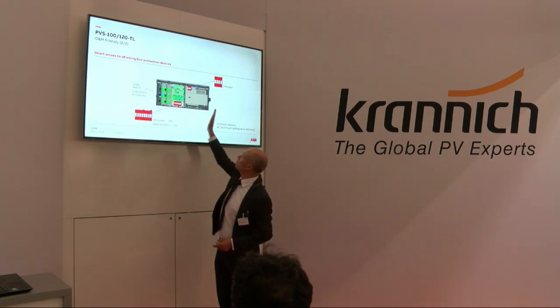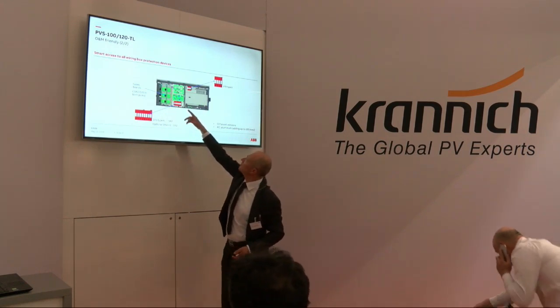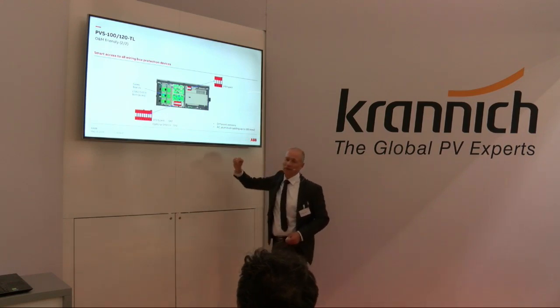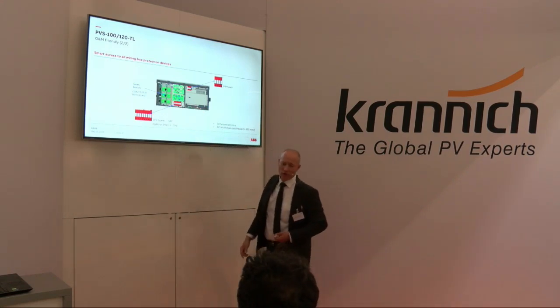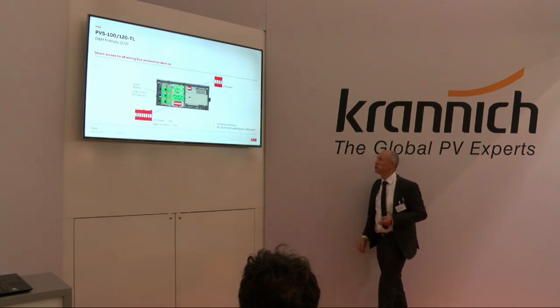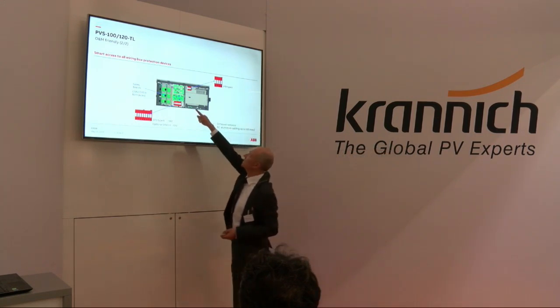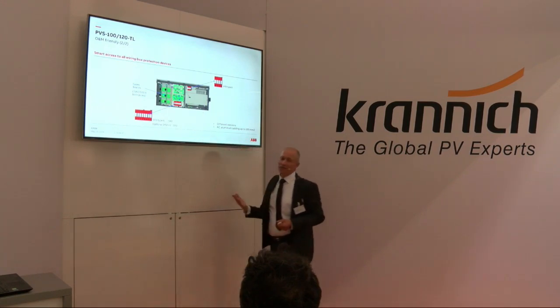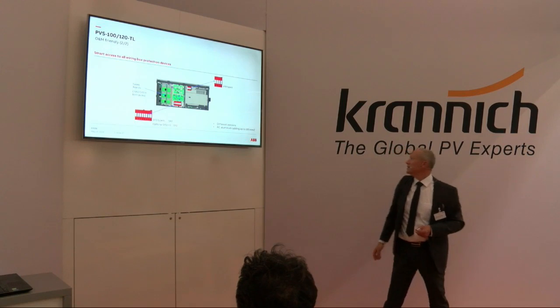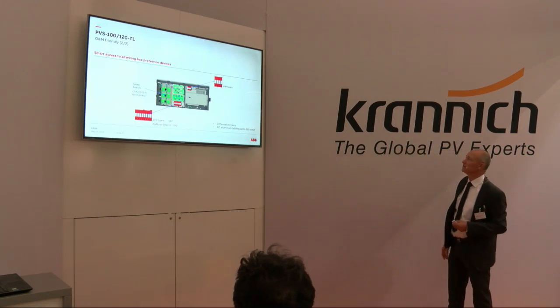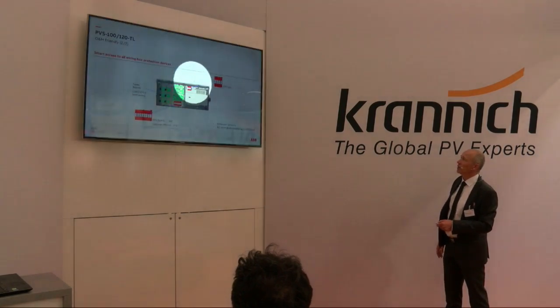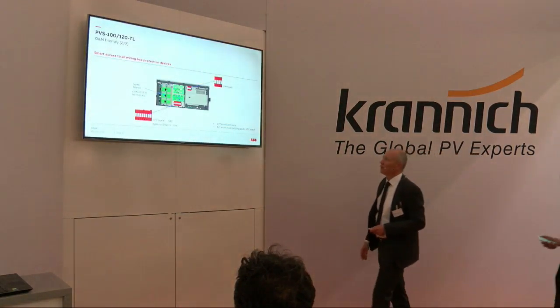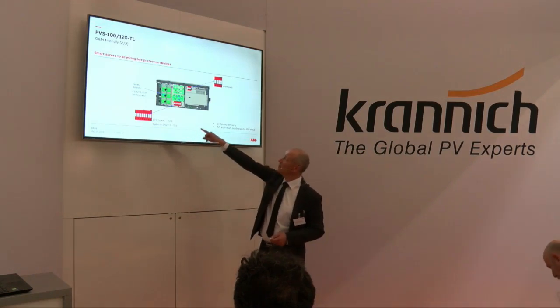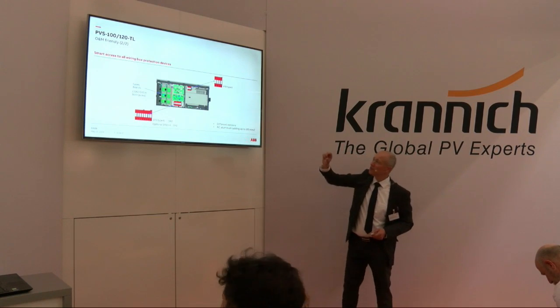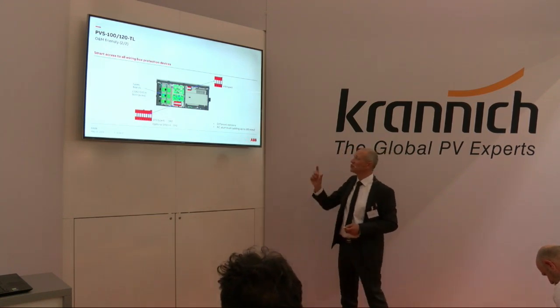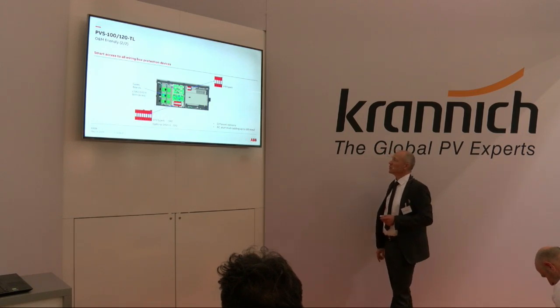And you see, this is around 1 meter, so you have 50 centimeters of space to bring the 185 square millimeter cables as a maximum into this box and connect them here. Here are the terminals, and you can connect 3 or 4 wire AC to this inverter, to the grid. On the AC side, we always have the SPD type 2. On the DC side we have 2 switches, so 3 MPPTs per switch, and 2 times means each 3 MPPTs, 1 switch.